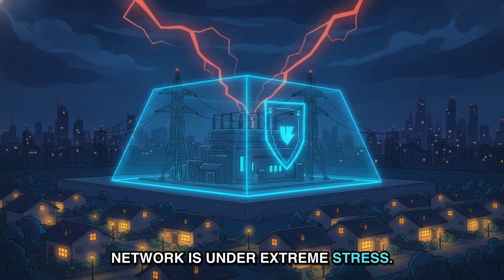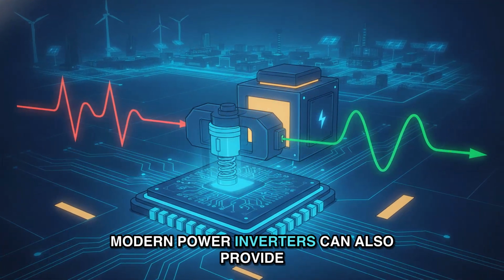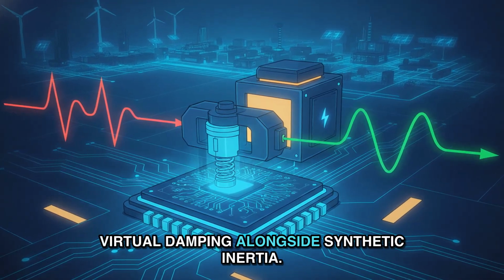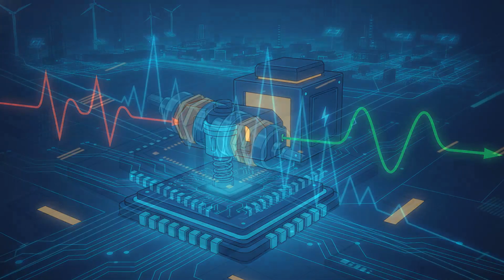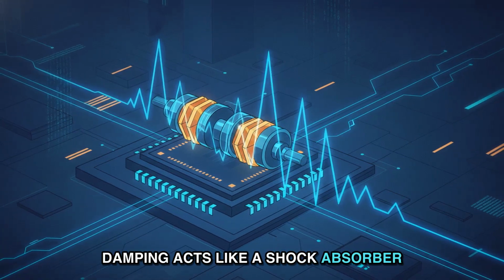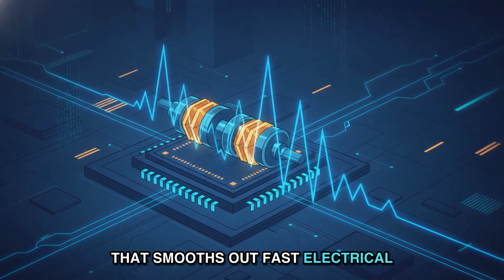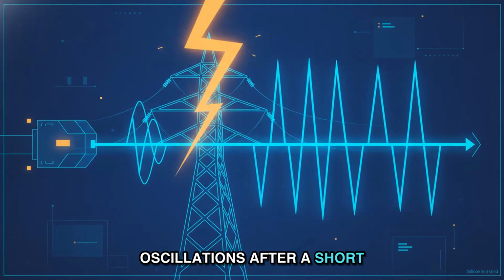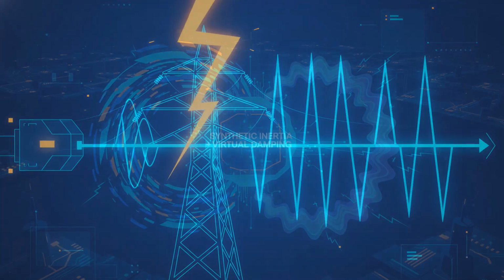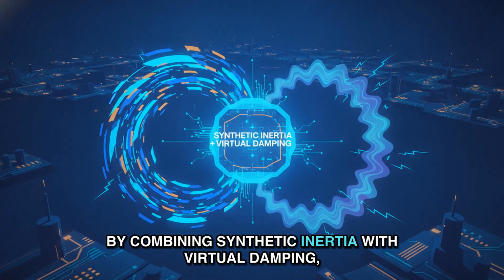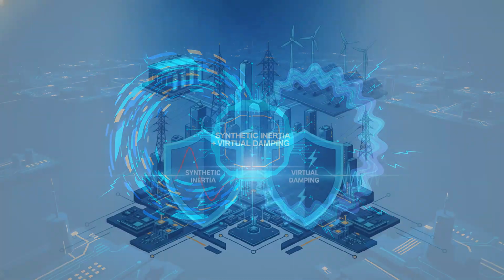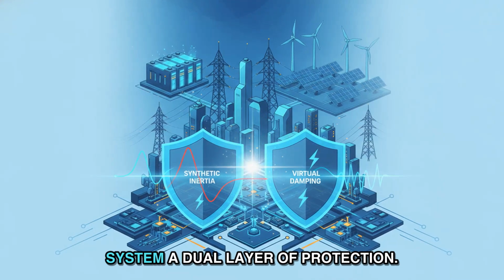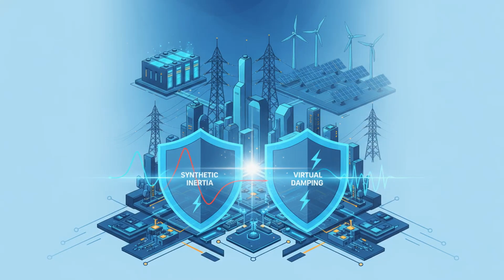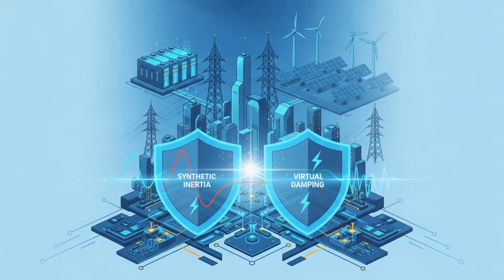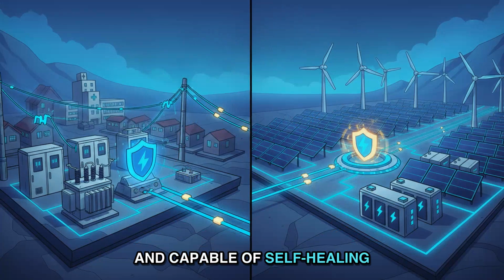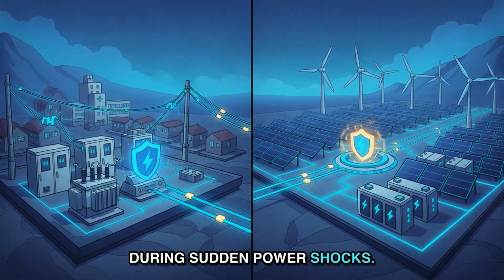Modern power inverters can also provide virtual damping alongside synthetic inertia. Damping acts like a shock absorber that smooths out fast electrical oscillations after a short circuit or lightning strike. By combining synthetic inertia with virtual damping, grid operators give the electrical system a dual layer of protection. The grid becomes resilient, flexible, and capable of self-healing during sudden power shocks.